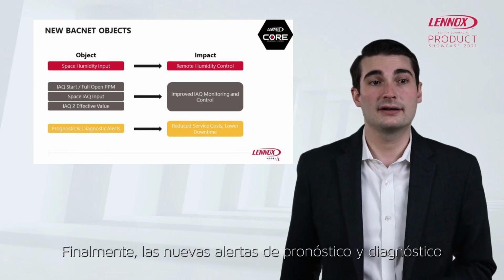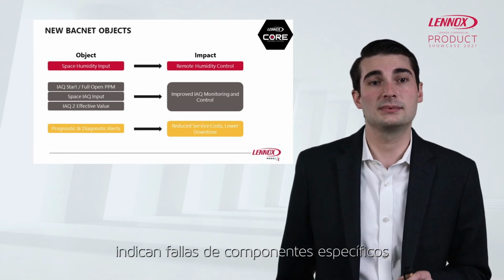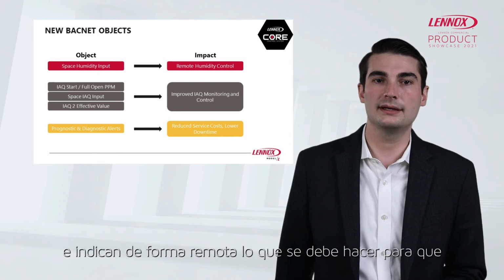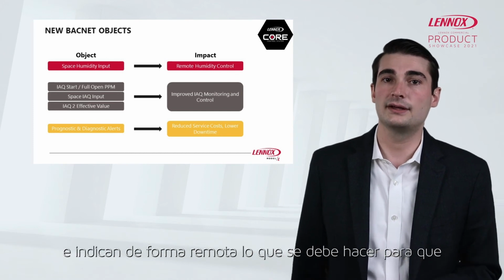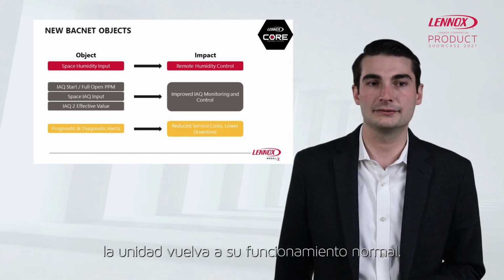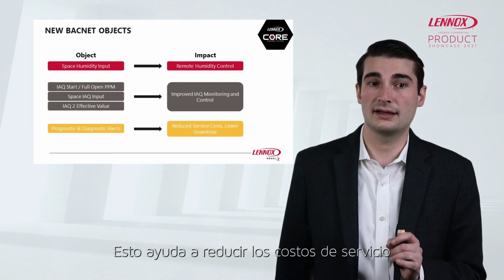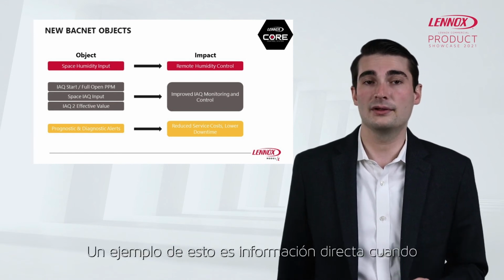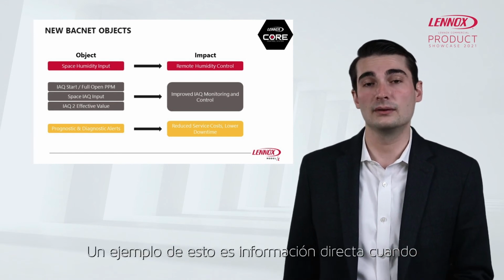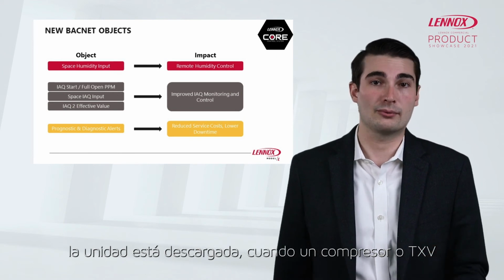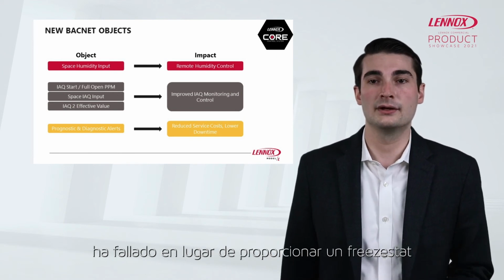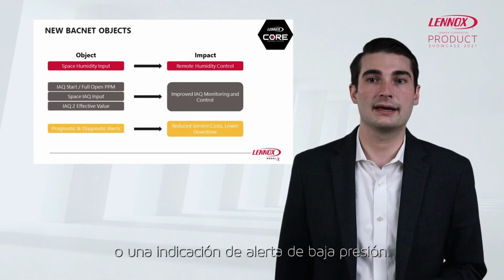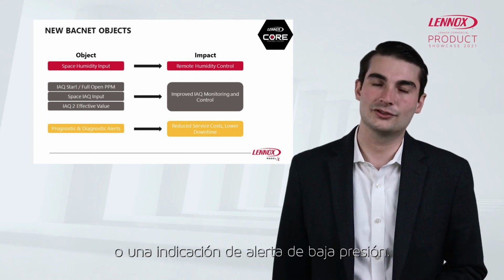Finally, the new Prognostic and Diagnostic alerts indicate specific component failures and remotely indicate what needs to be done to get the unit back to normal operation. This helps reduce service costs and lower downtime. An example is telling you directly when the unit is out of charge, or when a compressor or TXV has failed, rather than just providing a freeze stat or low pressure alert indication.